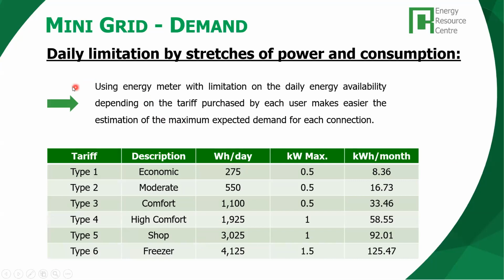In an off-grid mini grid, we have a situation where there will be a limited amount of electricity to be shared between the different customers or the different users. Okay, so this sharing has to be done in a proper way to avoid conflicts or tensions between the different customers. This is why smart meters that can have a limitation function are normally used. So if you are a type 1 user or customer, your meter will be equipped with a limitation functionality, so that you always stay at your level of consumption.